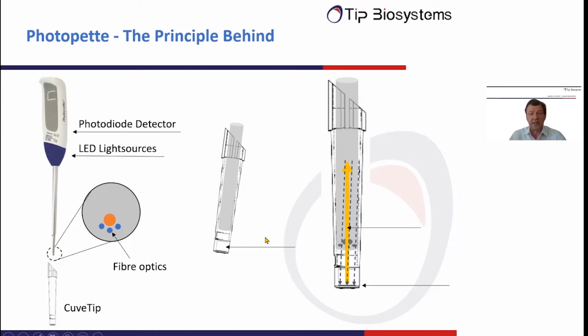And how does this work? Light is generated by the LED. It's guided through the fiber optics and is then transmitted through the liquid, which has entered the cavity of this tip. So the liquid is here. And the light is then absorbed in the liquid and is reflected on a mirror, which is part of the cuvette tip, and is then reflected back, collected by another light guide, and directed to the detector of the device. So here you see now the inserted cuvette tip into the liquid, and the liquid has entered the cavity.